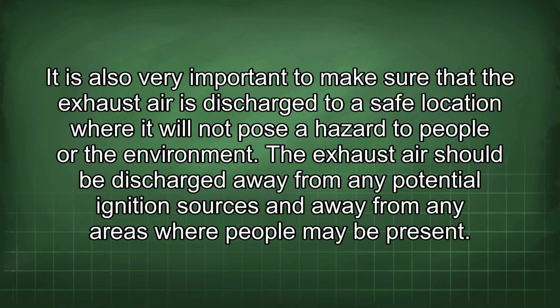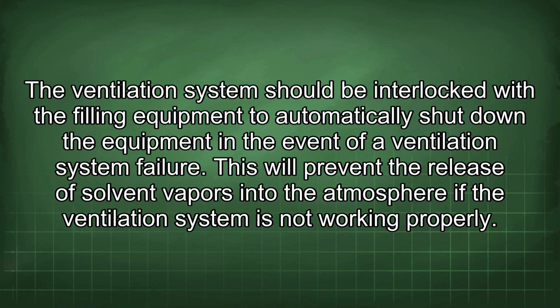It is also very important to make sure that the exhaust air is discharged to a safe location where it will not pose a hazard to people or the environment. The exhaust air should be discharged away from any potential ignition sources and away from any areas where people may be present. The ventilation system should be interlocked with the filling equipment to automatically shut down the equipment in the event of a ventilation system failure. This will prevent the release of solvent vapors into the atmosphere if the ventilation system is not working properly.